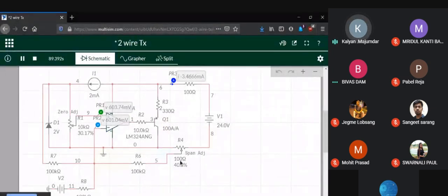জিরোটা কেটে গেছে। স্প্যান করেছিলাম 40, তার জন্য এখন কারেন্টটা হয়ে গেছে 3.4। জিরোতে হাত দিইনি, এখানে 0 মিলিভোল্ট ছিল, 0 মিলিভোল্টই আছে, কিন্তু যেটা 4 মিলি অ্যাম্পিয়ার ছিল, জিরোতে হাত না দিয়েও সেটা 3.46 হয়ে গেছে। So this needs to be readjusted.